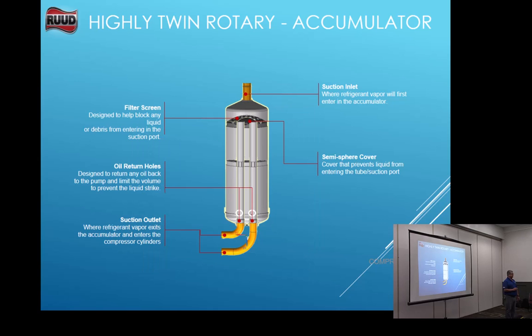We've got to have the tools to be able to do these jobs correctly. Okay? Just like this accumulator will not save you. Let it run for 20 or 30 minutes before you think about adding refrigerant in charge mode. Because can we charge it? And if we can, and we fill it up with liquid and fill it up and fill it up till it overflows this tube and gets in here to the bottom of that rotary compressor. And this looks big on the screen, but it doesn't hold that much refrigerant. Okay? So just keep that in mind going forward.